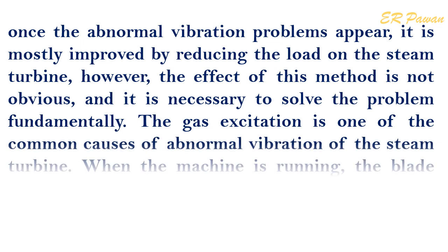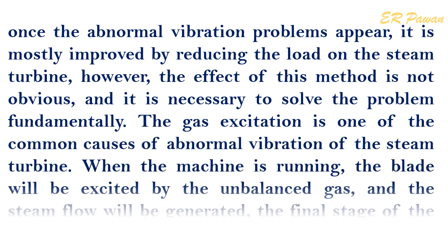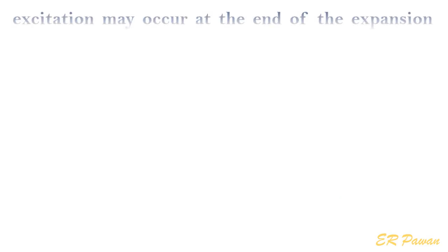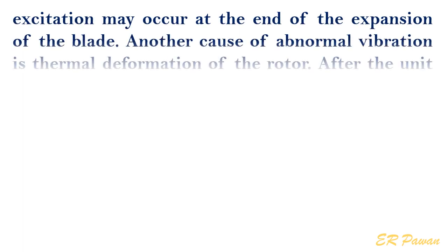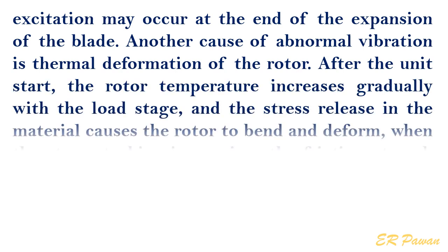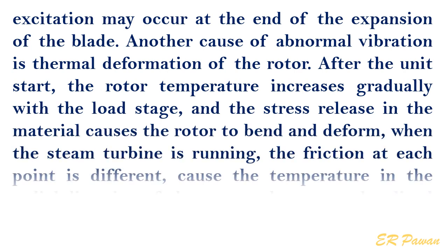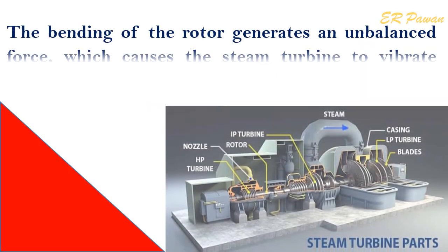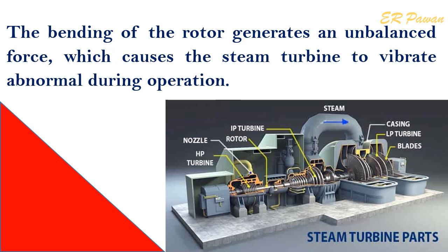Gas excitation is one of the common causes of abnormal vibration. When the machine is running, the blade will be excited by unbalanced gas and steam flow will be generated. Excitation may occur at the end of the expansion of the blade in large units. Another cause of abnormal vibration is thermal deformation of the rotor. After the unit starts, the rotor temperature increases gradually with the load stage, and stress release in the material causes the rotor to bend and deform. When the steam turbine is running, friction at each point differs, causing uneven temperature in the radial direction of the rotor, and localized heating causes the rotor to bend thermally. This bending generates an unbalanced force, which causes abnormal vibration during operation.